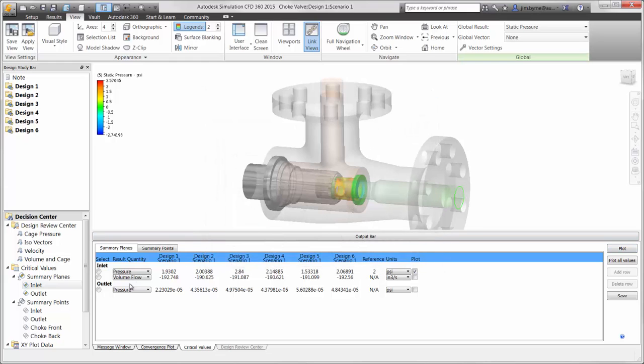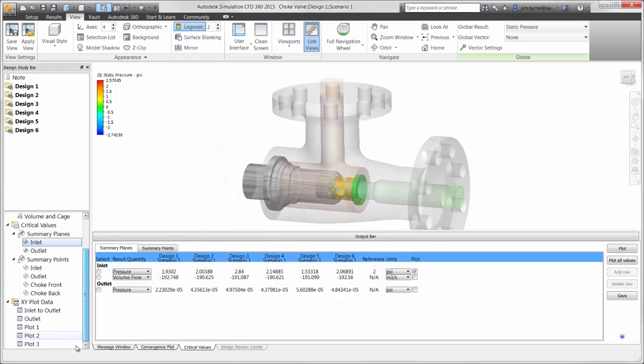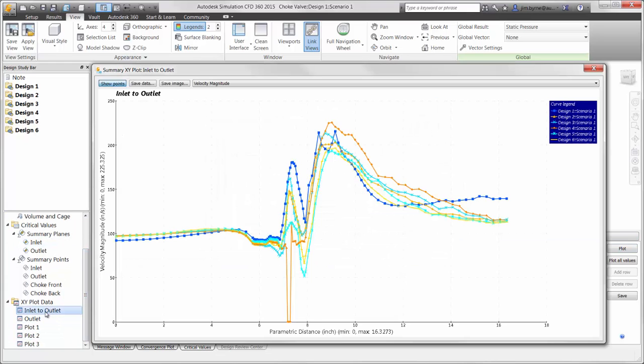The XY plot that we viewed earlier can also be saved in the decision center so we can view and compare the results for all studies at the same time. This way we can view the results for pressure and velocity from the inlet to the outlet of the valve. Once again the shape of the holes in the fifth cage design is clearly going to perform the best.